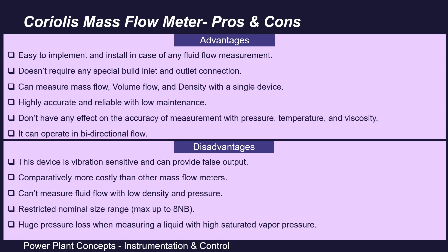Disadvantages include: measurement is affected by any gas inclusion in the fluid flow, the device is vibration sensitive and can provide false output, and it is comparatively costlier than other mass flow meters. It has a limited temperature range, cannot be used to measure fluid flow with low density and pressure, is restricted to nominal bore line sizes of up to 8 inches, and produces a large pressure loss when measuring liquids with high saturated vapor pressure.